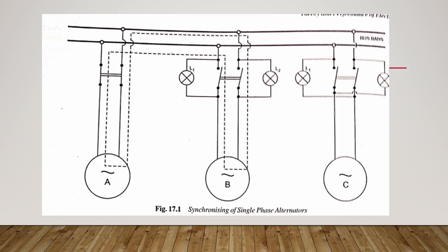Let alternator B be connected to the bus bars to which alternator A is already connected. The prime mover of alternator B is started and brought up close to the rated speed. The alternator is then excited, and its voltage is raised by increasing its excitation to that of the bus bars or running alternator. Synchronizing lamps L1 and L2 are connected across the double pole paralleling switch of the incoming alternator B.